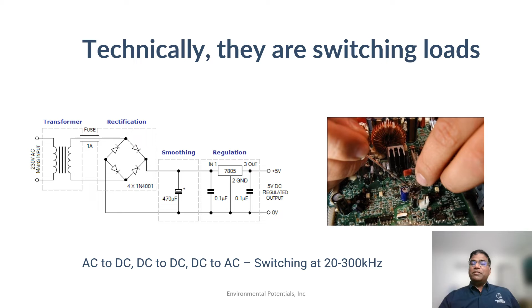Okay, so the bottom line is now we are moving away from traditional loads to switch mode power supply loads. So what is the change that we switched from traditional loads to the switching loads created? I would say this just creates electrical noise in the system. This used to be the traditional sine wave for a traditional linear load. Now the non-linear load is adding all the hash, noise, transients, high frequency noise, and also harmonics on the sinusoidal wave, making disruptions in the voltage.